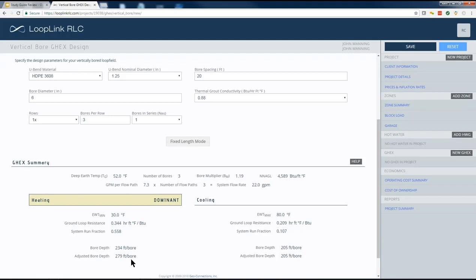So you can see the considerable impact that grout conductivity has on your design, and keep in mind that grout conductivity is something that you as a designer can specify. You have control over it, and it's something that when a driller follows a recipe, they'll actually be able to deliver specifically. So going from a 0.4 to a 0.88 grout, you can see dropped quite a bit off of our ground loop design. And to give you an idea, as I said, this is just bentonite and water. A 0.88 is bentonite and water and 200 pounds of silica sand in the mixture.